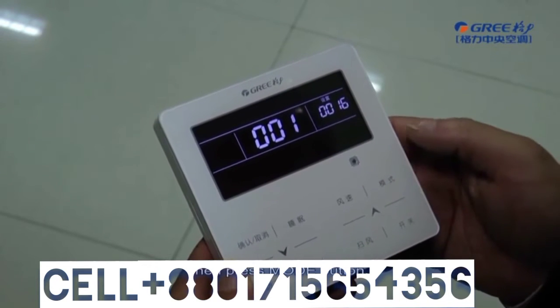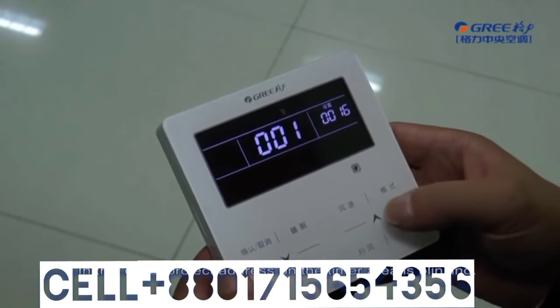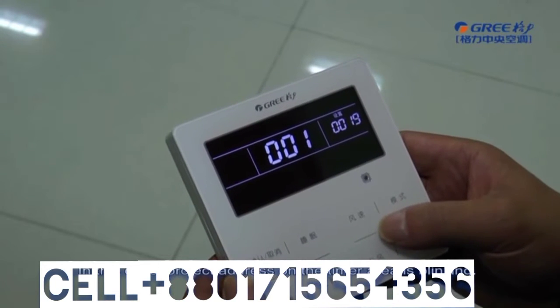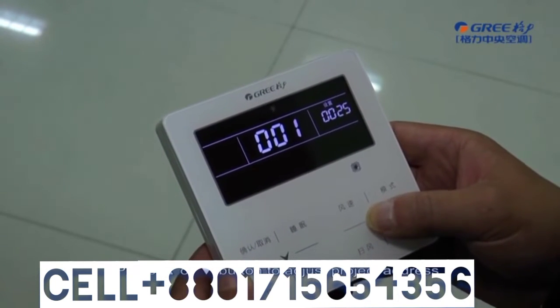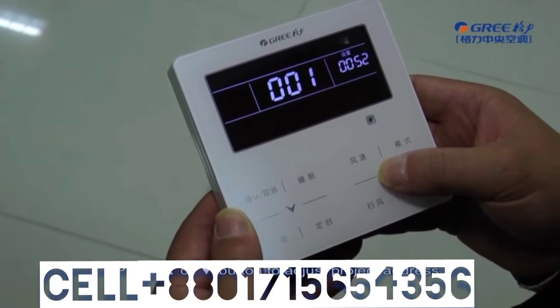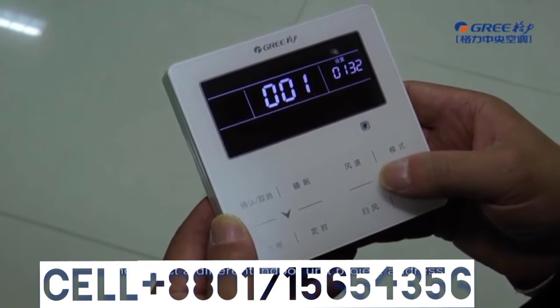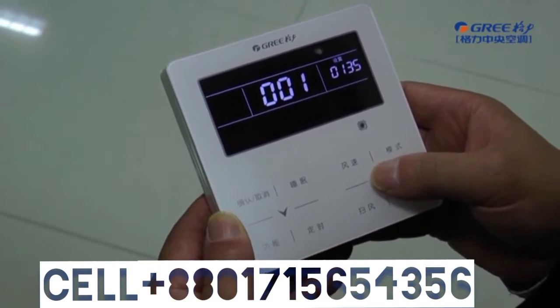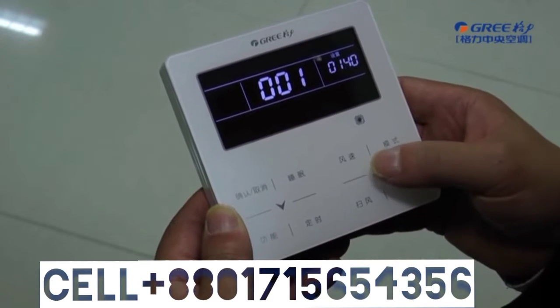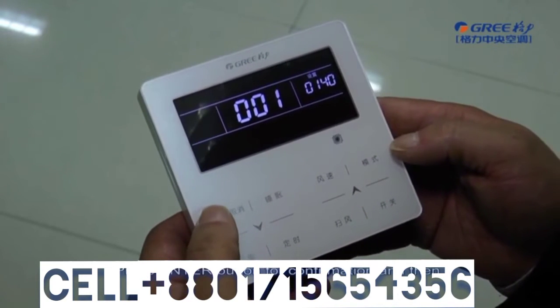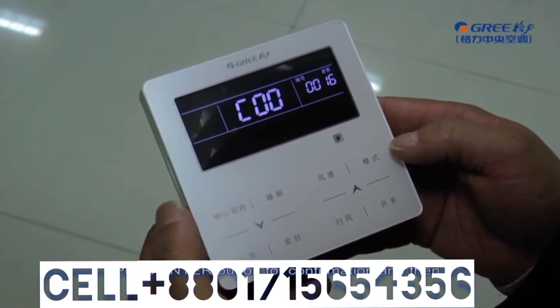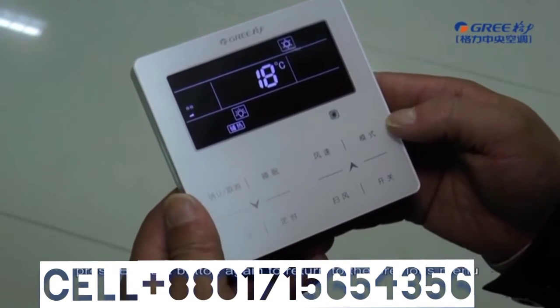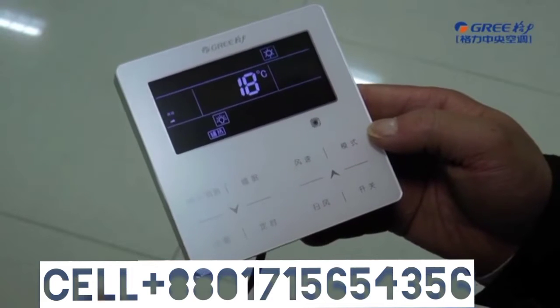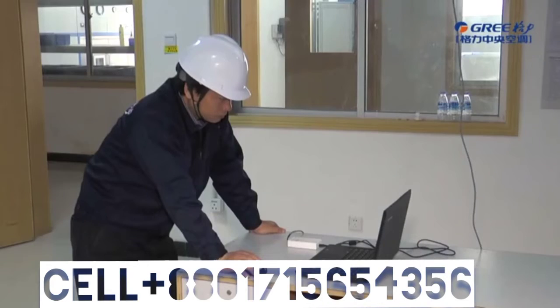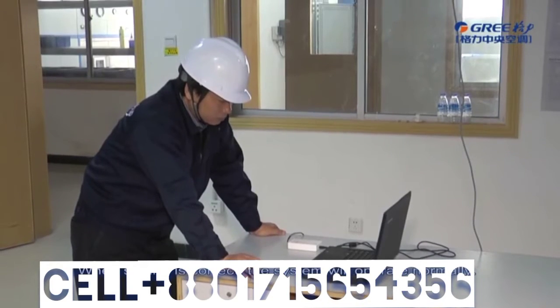Then press mode button. In this case, project address on the timer area is blinking. Press up or down button to adjust project address and select a different indoor unit project address. Press enter button for confirmation and then press enter button again to return to the previous menu. When setting is correct, the system will operate normally.